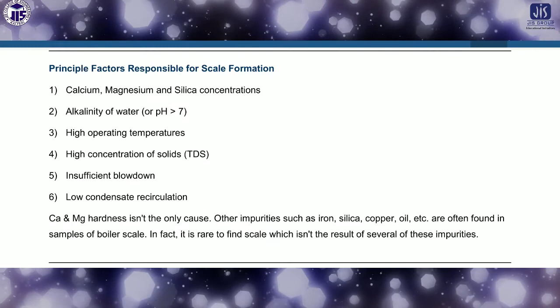Now, what are the principal factors which are mainly responsible for the scale formation? This is the calcium, magnesium and silica concentration. These are mainly responsible for the scale formation. Alkalinity of the water sample is another factor which we have to control, because it is also responsible for the scale formation. High operating temperature, high concentration of solids, insufficient blowdown, and low condensate recirculation. So all these things are responsible for the scale formation.